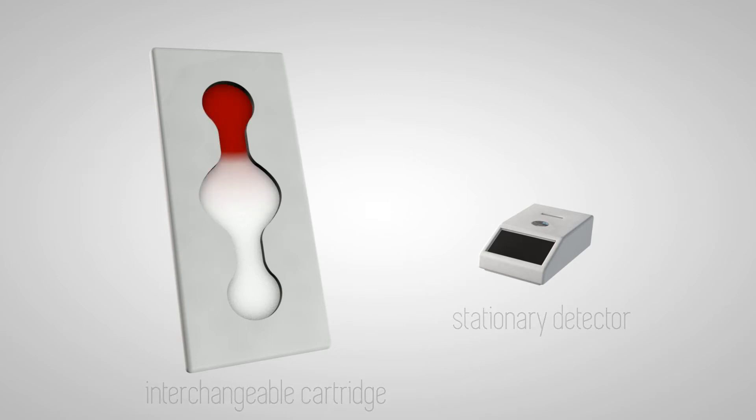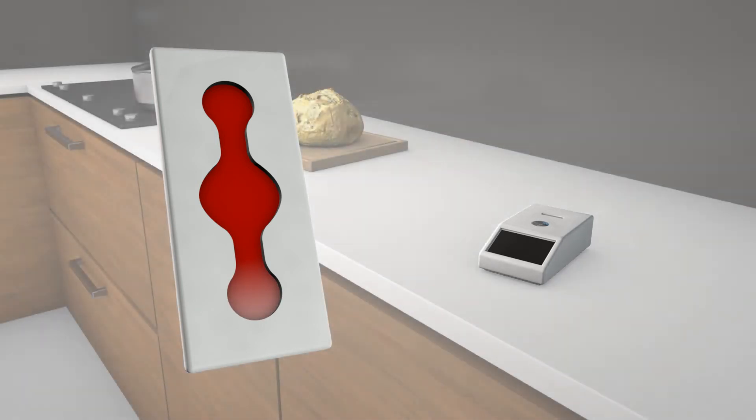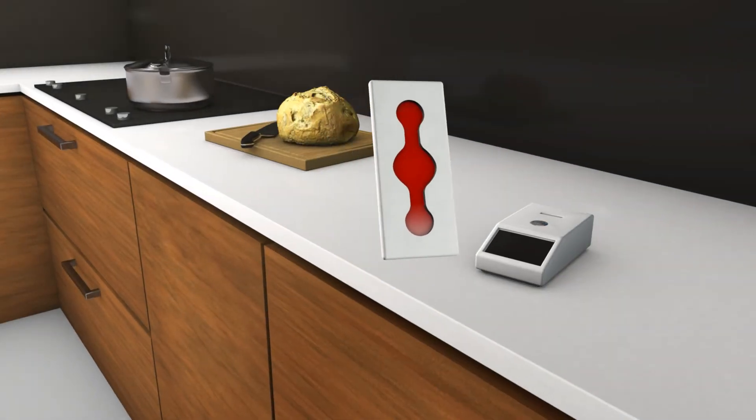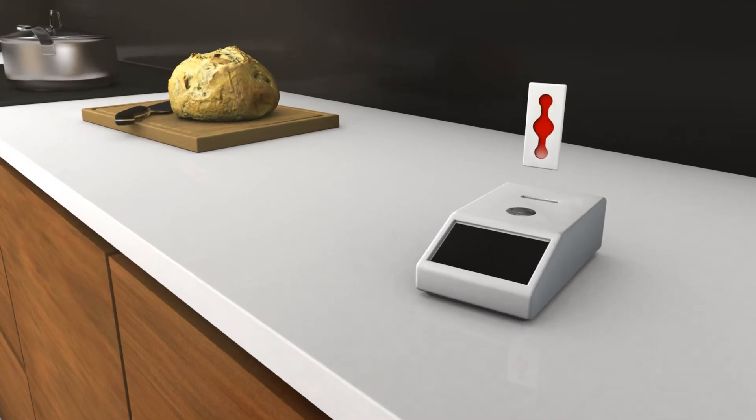The patient inserts a droplet of blood in a cartridge. Inside the cartridge, the blood is filtered and the fluid is transported to a reaction chamber via capillary transport.